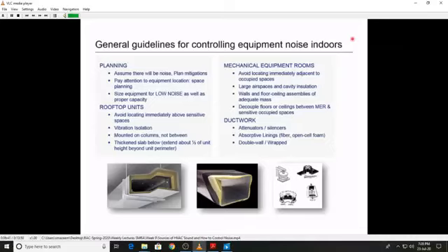In terms of mechanical equipment rooms, in other words, having all the large noise-making equipment inside the building, again, avoid locating those rooms near occupied spaces. Use large air spaces and cavity insulation in the walls, ceiling, and floor surrounding the equipment room. Make sure that your wall and floor-ceiling assemblies have a lot of mass so that, again, they break that path. And decouple the floors and ceilings between a mechanical equipment room and any sensitive occupied spaces.